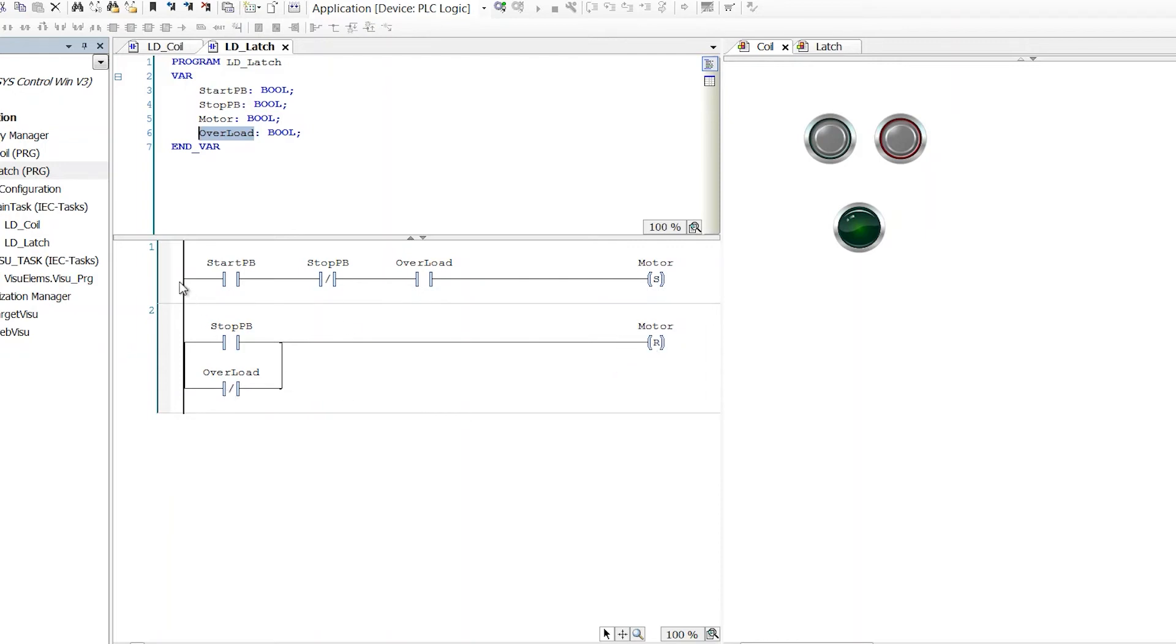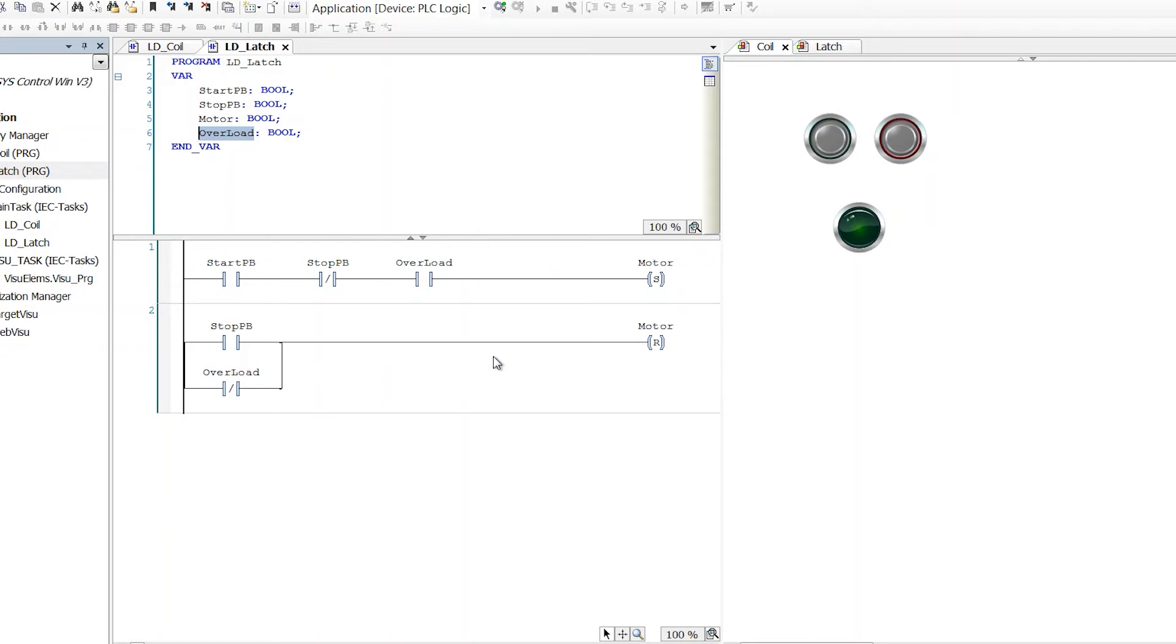And this can be convenient in some cases because now we can have several conditions that turn the thing on and several conditions that turn the thing off. And that can make it a little bit more manageable to parse mentally. That being said, I would generally encourage don't use set and reset. Don't do the latch and unlatch thing.